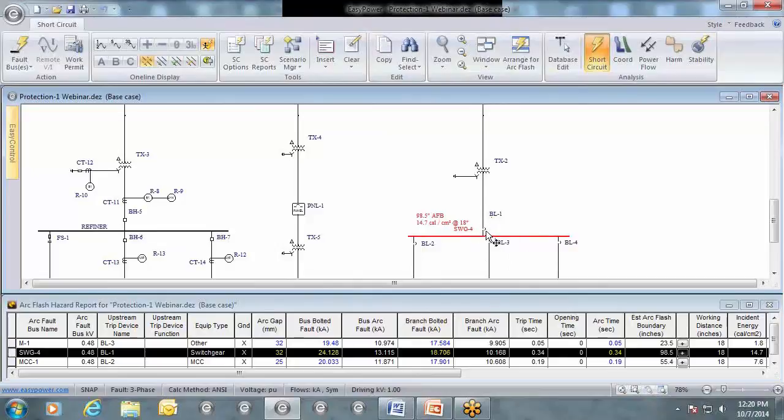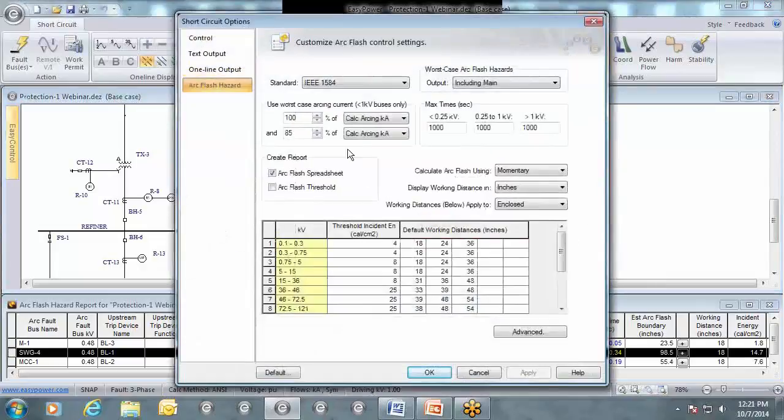In order to do that, you'll want to make sure that your main device is isolated and barrier protected to ensure that if there is an arcing fault downstream of that main, that device does not become engulfed within the arc.